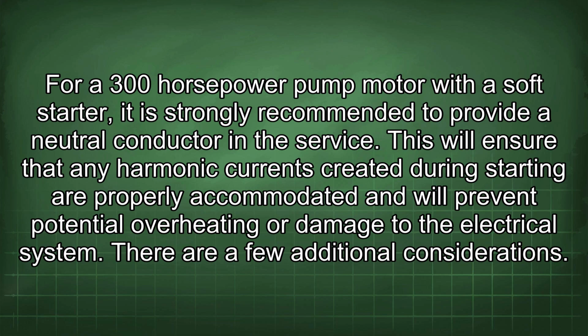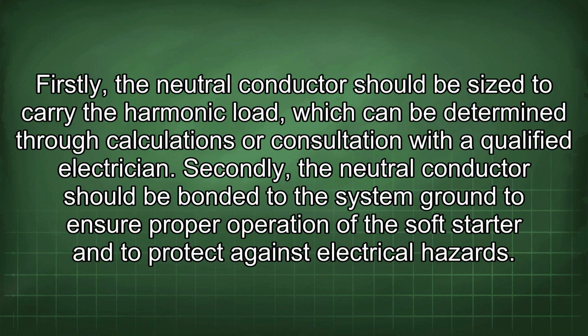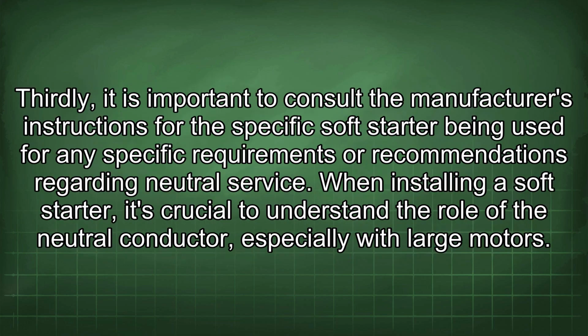There are a few additional considerations. Firstly, the neutral conductor should be sized to carry the harmonic load, which can be determined through calculations or consultation with a qualified electrician. Secondly, the neutral conductor should be bonded to the system ground to ensure proper operation of the soft starter and to protect against electrical hazards. Thirdly, it is important to consult the manufacturer's instructions for the specific soft starter being used for any specific requirements or recommendations regarding neutral service.